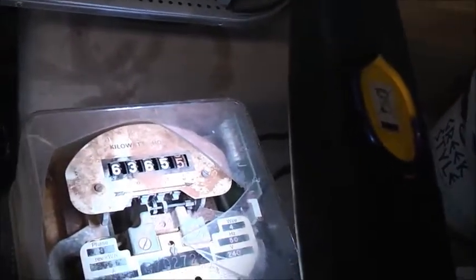Get the wheel moving really freely, no obstructions in the mechanics, and do an accuracy load test on it as it is, I think. I've got to get a lot of crap out of this to do that though, because any slight interference in the mechanism can give me an error in the reading.